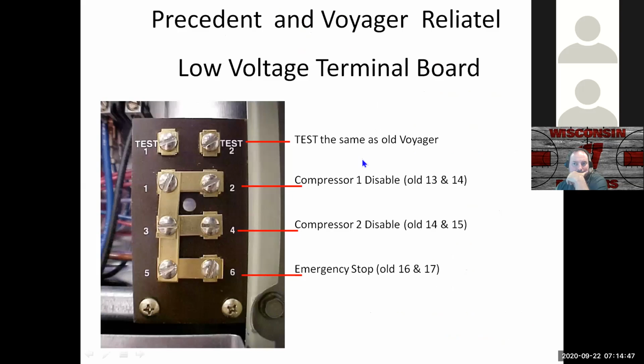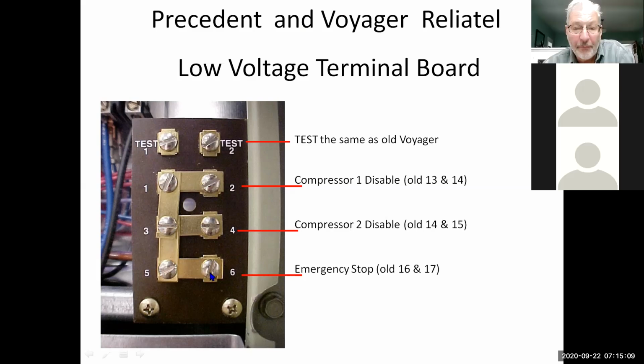The new board on these units still has the test 1 and test 2 on the Reliatel units, and we only have 6 terminals here because we've put all the other terminals on the main board. So compressor disable is 1 to 2. Compressor 2 disable is 3 to 4. And again, emergency stop is going to be 5 to 6. If you're looking at these, what you want to make sure is that they're clean, they're not corroded, the screws are tight. If it looks like a capital E, all the letters are in place, okay? All the jumpers are in place. So make sure that you take a look at this if you're having issues or something's not working just right.